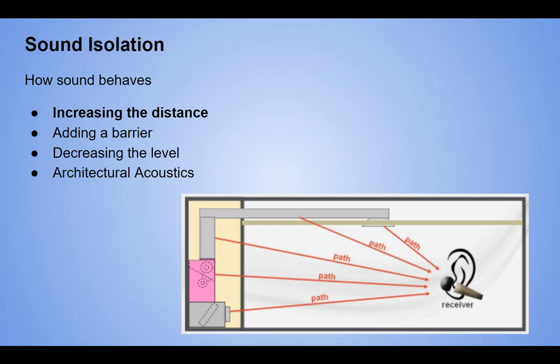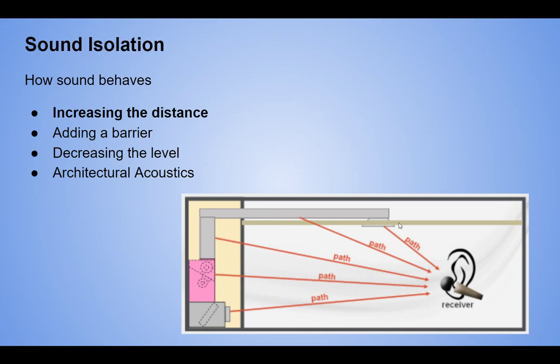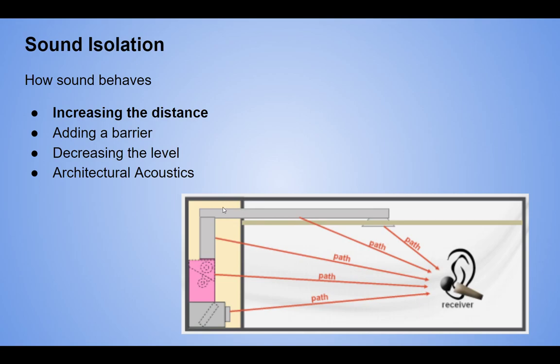Increasing distance is your friend — the easiest thing to do first, especially early in design. Claim your space, keep things away. In a concert hall design, I'd draw a big thick line on the plan called an acoustic isolation joint. Basically, if you're going to cross that line you've got to do specialty construction — it forces penetrations away. If you punch through the line, you've got to do something on that side so noise doesn't break through the duct.